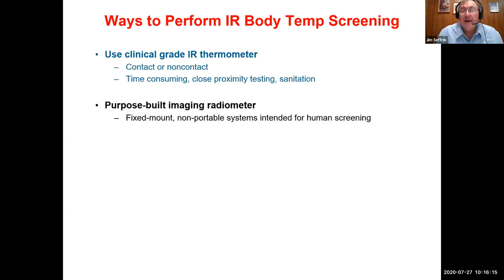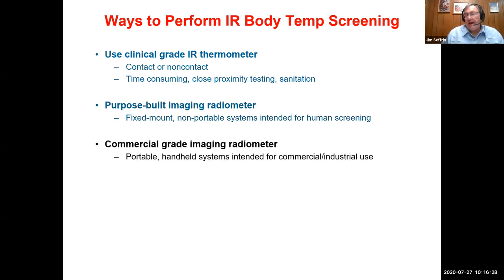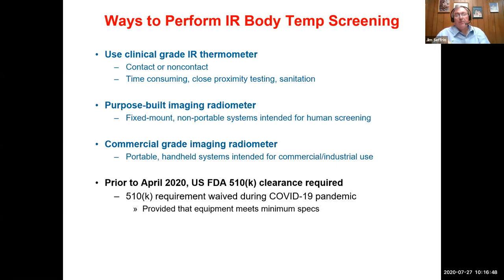A second way to perform infrared body temperature screening is to utilize a purpose-built imaging radiometer. These are typically fixed mount, non-portable systems intended for human temperature screening. They're purpose-built instruments. A third way, and this is where home inspectors come into play, you can use a commercial grade imaging radiometer. These are typically portable handheld systems intended initially for commercial and industrial use. Provided they meet certain protocols, they can be used for elevated body temperature screening. Now, prior to April of this year, the United States Food and Drug Administration required that any instrument that was going to be used for human temperature measurement or diagnosis had to have a 510K clearance.